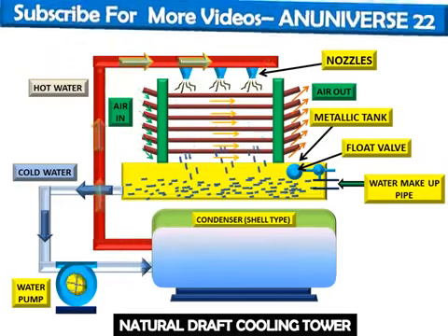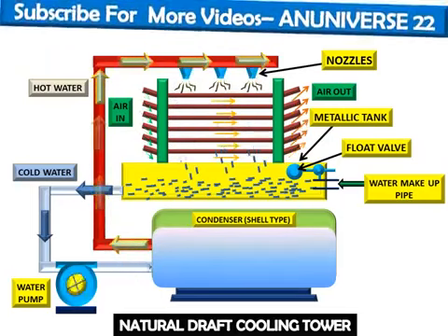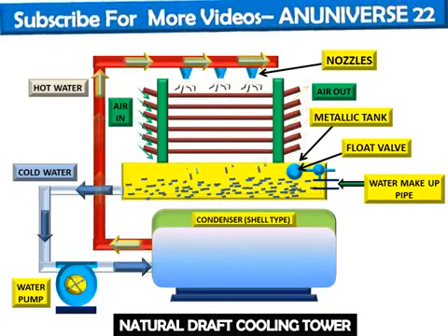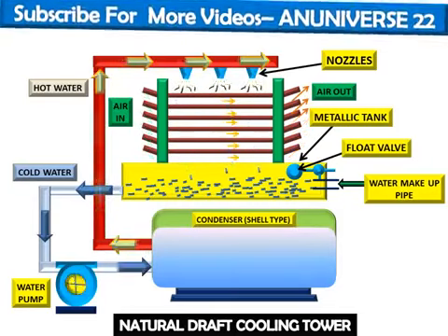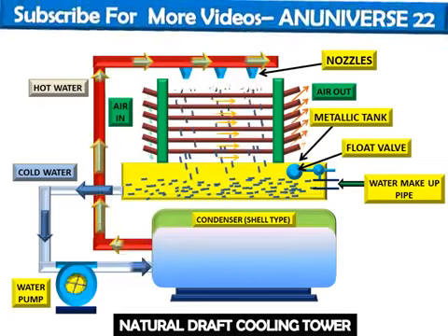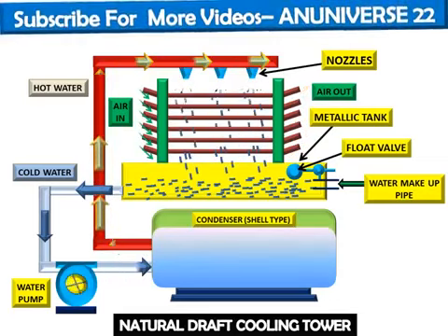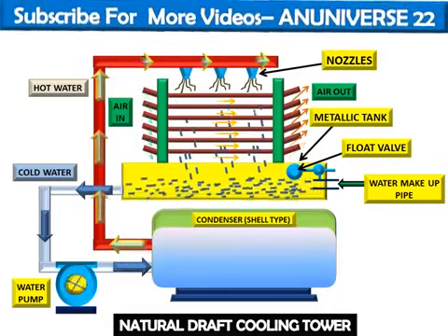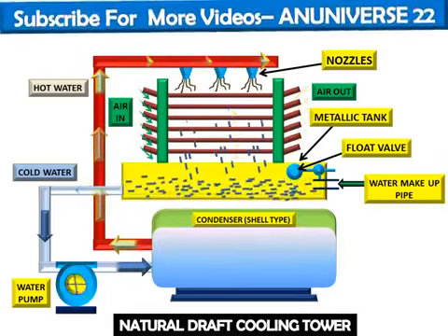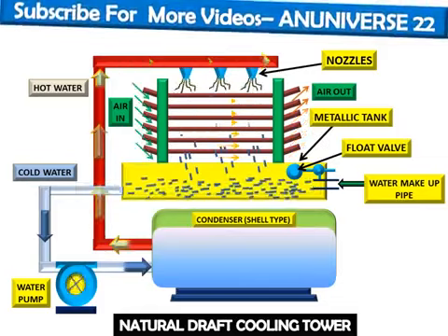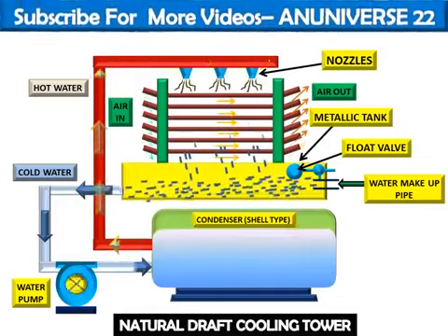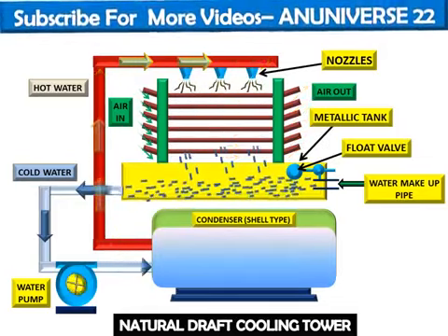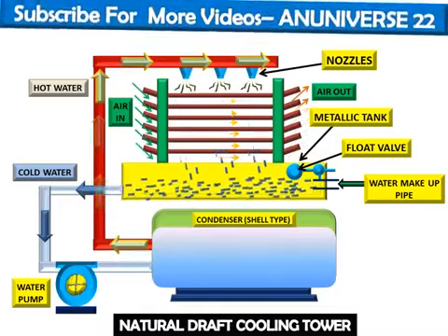Since the heat transfer from the water to air is dependent upon the surface of water exposed to the air stream, a spray nozzle having finer spray pattern is essential for good performance of the cooling tower.